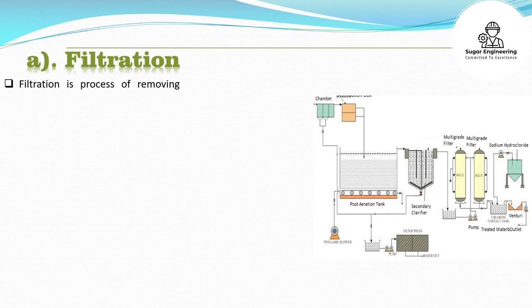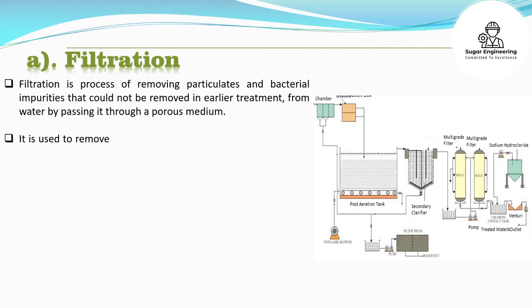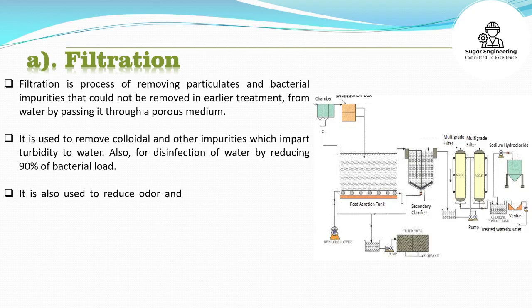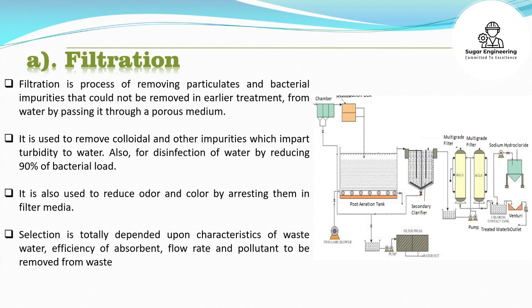Filtration is the process of removing particulates and bacterial impurities that could not be removed in earlier treatment, by passing water through a porous medium. It is used to remove colloidal and other impurities which impart turbidity to water, and for disinfection of water by reducing 90% of bacterial load. It is also used to reduce odor and color by arresting them in filter media. Selection is totally dependent upon characteristics of wastewater, efficiency of absorbent, flow rate, and pollutant to be removed.